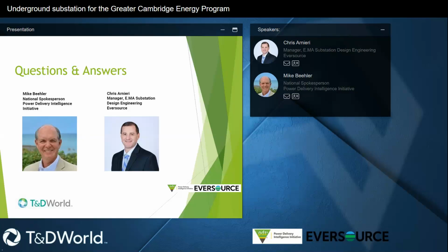With the battery rooms within the substation—I didn't go through the nitty-gritty—but they're separated, one on either side of the substation, with a whole bunch of other stuff in between. So we purposely kept them completely isolated from each other. The ventilation is the same, accounting for hydrogen storage or buildup that could happen. Those rooms are fully ventilated, and any hydrogen that builds up on the ceiling gets pulled and sucked out by the ventilation system.